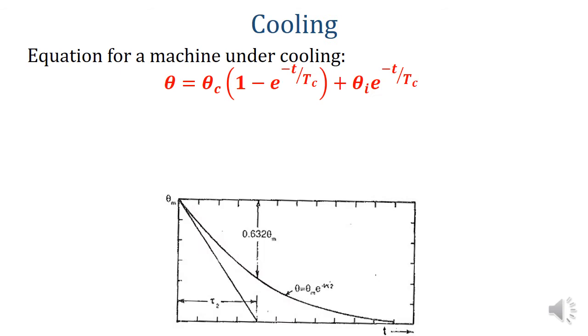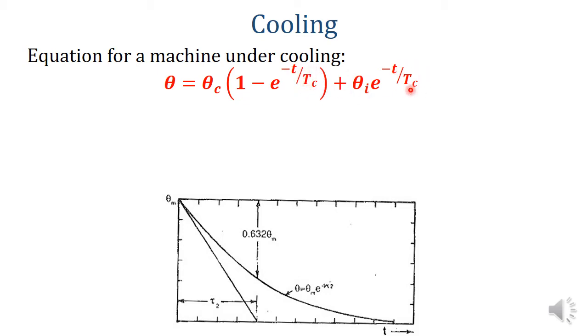If the machine is allowed to cool, a similar equation can be written: theta equals theta_c times (1 minus e raised to minus t by tc) plus theta_i times e raised to minus t by tc. The equation is almost similar; only the two terms theta_c and theta_i are different, and the heating time constant is replaced by the cooling time constant.